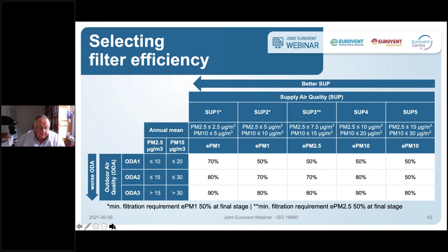We have here two remarks for these higher supply air quality classes. The minimum filtration requirement is that the final stage of the air filtration should be at least an ePM1 50% filter. I will explain that on the next slide. So we know now that for our example, we need an ePM1 80% filtration. How to get that?